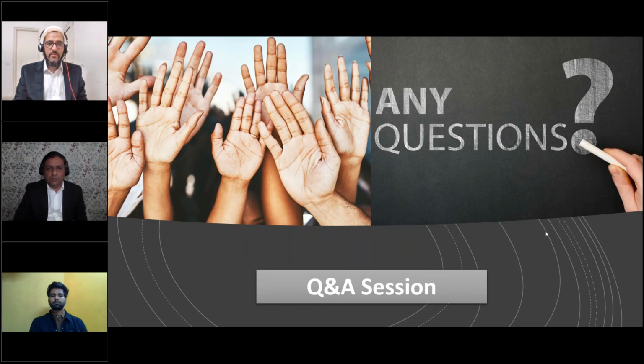So for example, the design team wants to do some kind of test to understand their confidence. Once they exit the design phase, they exit with confidence that their product is meeting the requirement. And when they go into the design verification phase, they are confident that we have already tested internally and all the tests are passing, so we can go ahead. So to answer your question, design verification is the formal testing, but there can be testing at many stages: prototype stage, your internal testing stage, or design freeze stage.